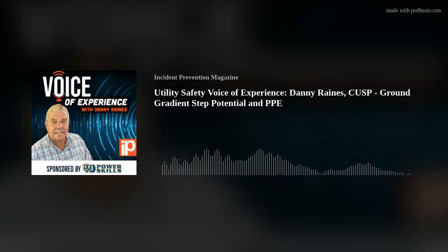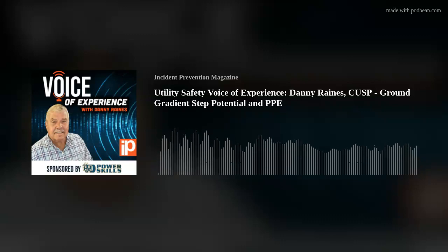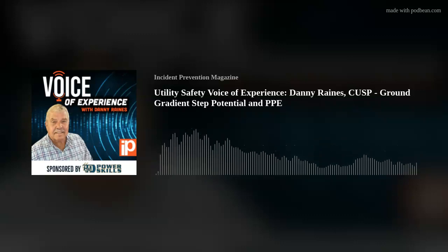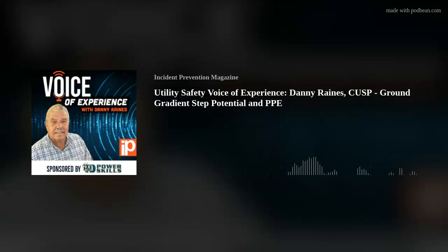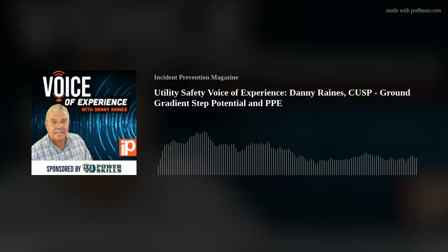Don't even set it hot. If you've got to, get an outage on it, prearrange an outage, and de-energize it. That's Article 120 in the NFPA 70E. The best way to avoid a flash or electrical shock is to have it locked out and tagged out. So that's by far the best way.